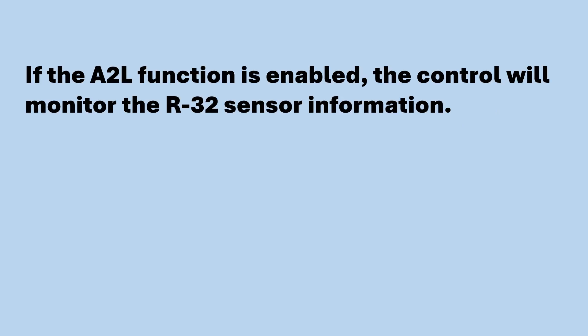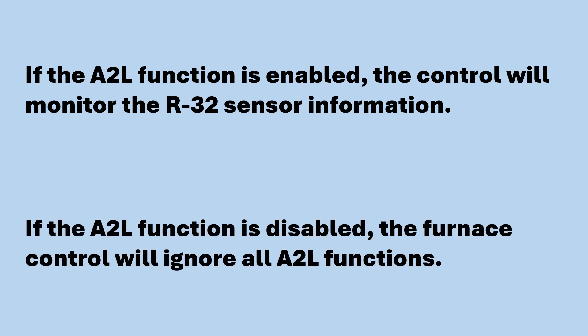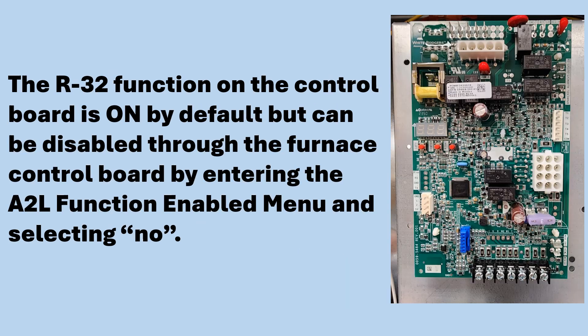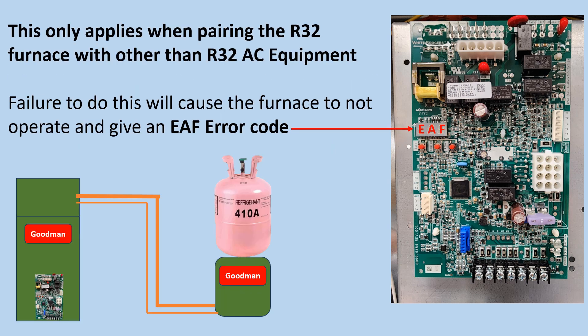If the A2L function is enabled, the control will monitor the R32 sensor information. If the A2L function is disabled, the furnace control will ignore all A2L functions. The R32 function on the control board is on by default, but can be disabled through the furnace control board by entering the A2L function enabled menu and selecting no. This only applies when pairing the R32 furnace with other than R32 AC equipment. Failure to do this will cause the furnace to not operate and give an EAF error code.